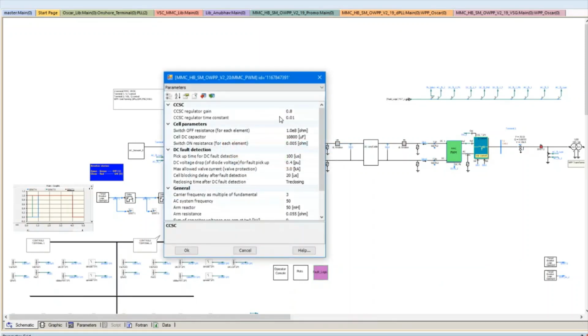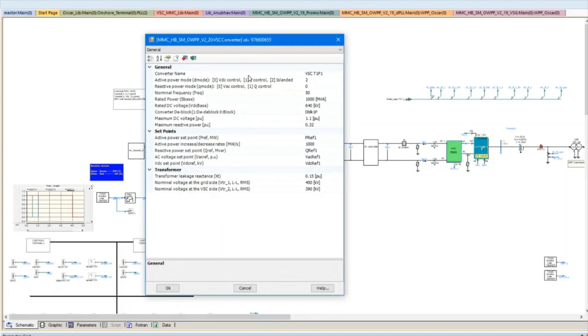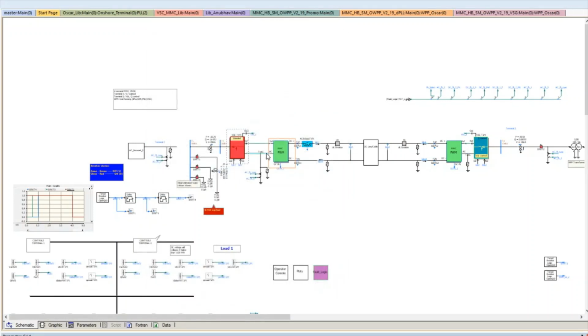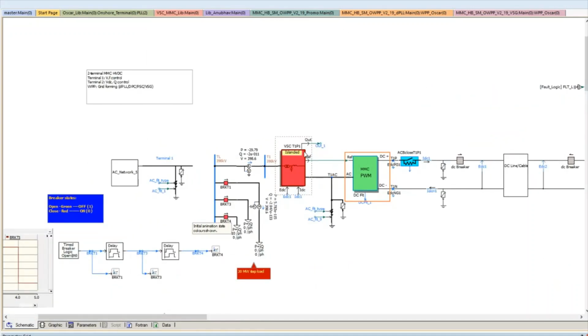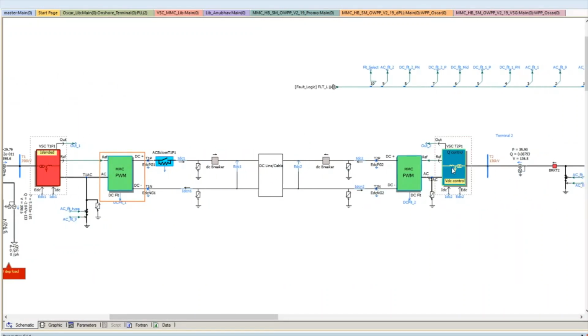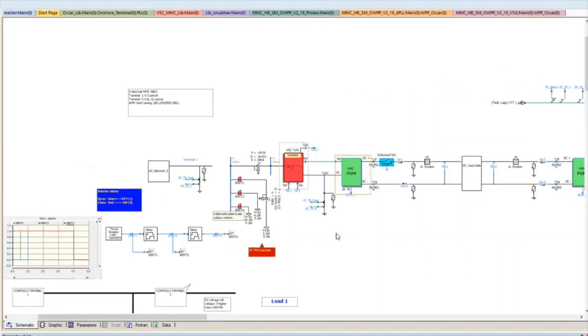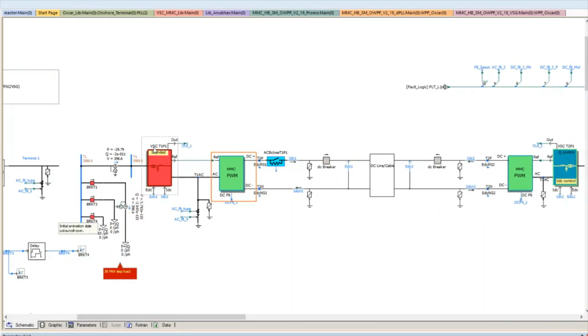The MMC control modes. In this terminal, you can set up the different parameters: resistances, capacitor values, inductors, filters, etc. And you have the choice to set which control mode you want for the MMC. Right now the onshore is set to islanded control mode, and it's shown here by this color, while the offshore is set in VDC-Q control, and it shows here in this color. The two models are the same, so the offshore MMC and the onshore MMC are the same.